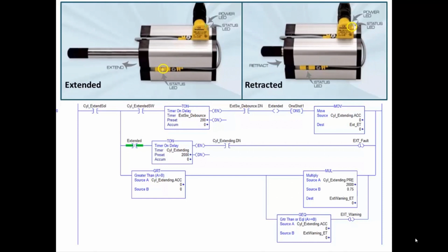Now this logic is written in what I call sequential instructions, meaning that it doesn't follow electrical characteristics. As you can see, I have a TON, timer on delay, OTE, one shot, and a move. If this were an electrical circuit, the extend OTE and the move are considered output instructions or loads in typical electrical description.